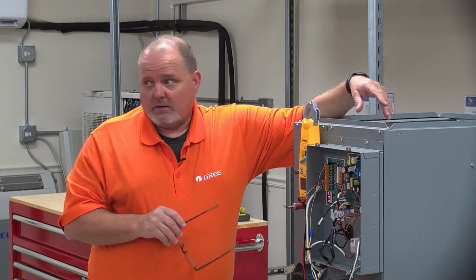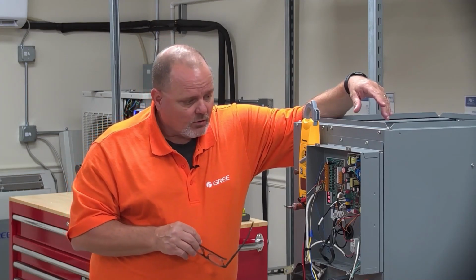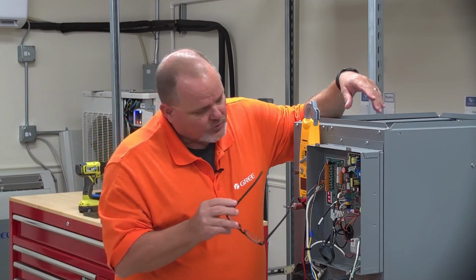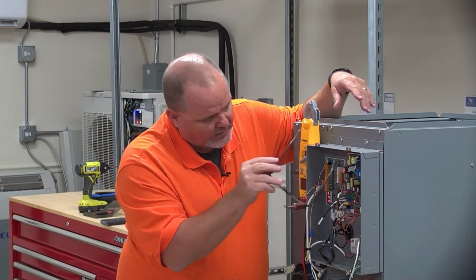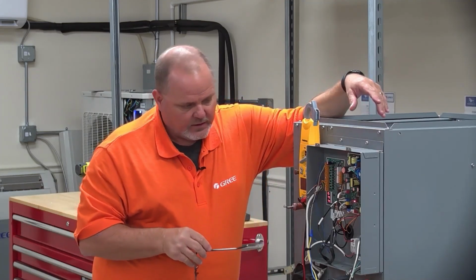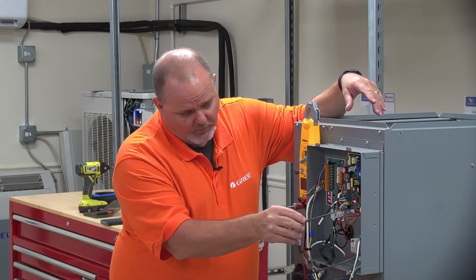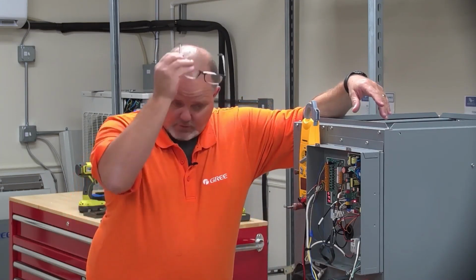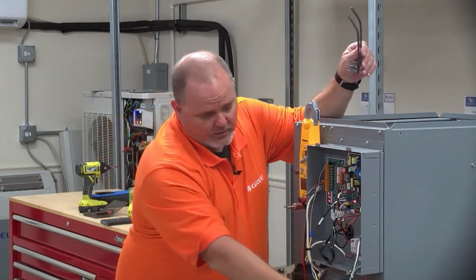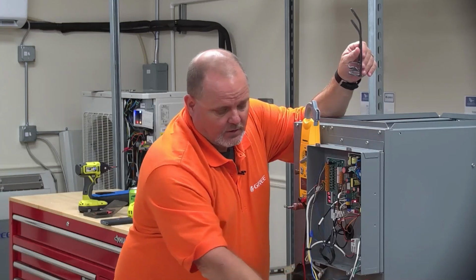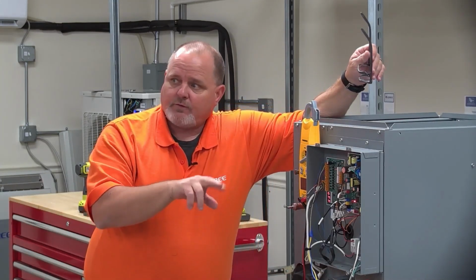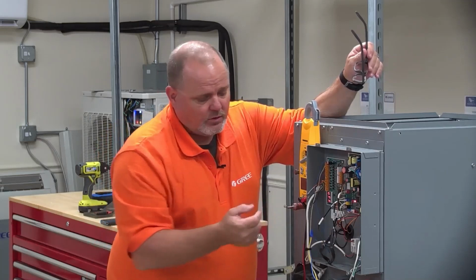Shouldn't affect it in heating mode. So other than that, there's really nothing else you need to do or tie into that board. And again, you're just going to put your 120 volts to it. You can grab that right off your furnace. That's right here. You'll see this little power cord coming up. So you can grab your 120 volts off the furnace and just run it up into your coil here.